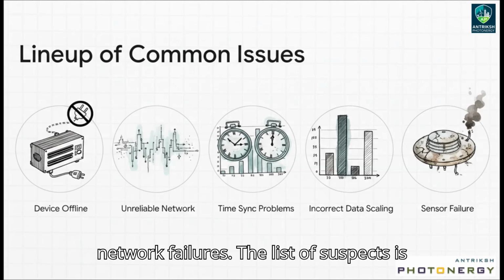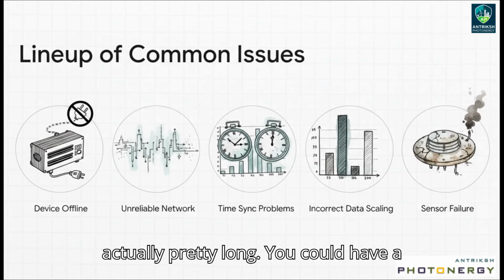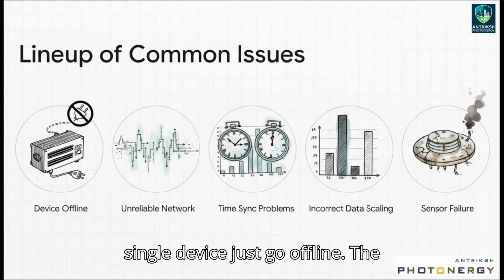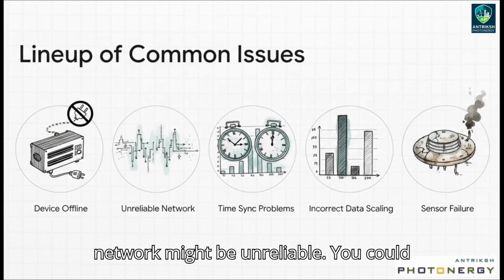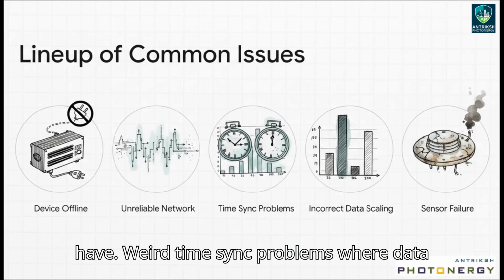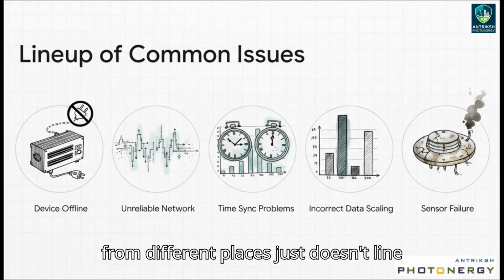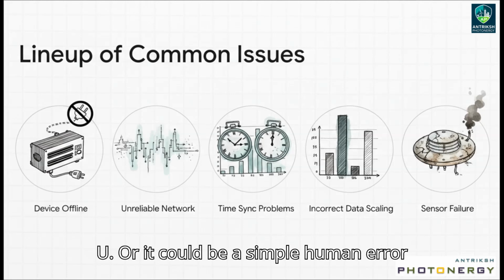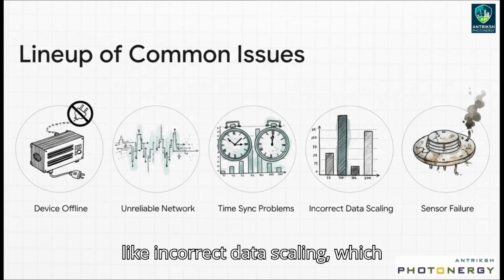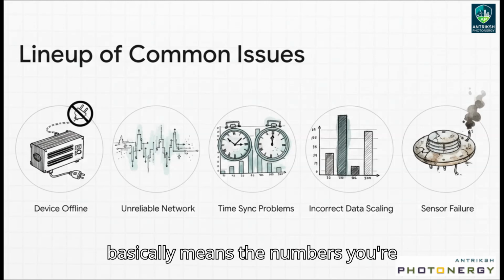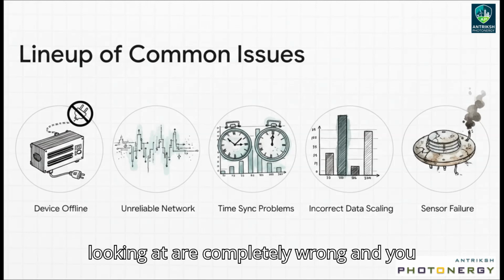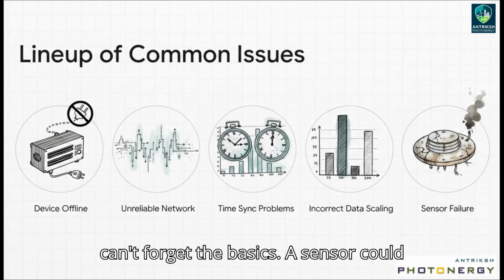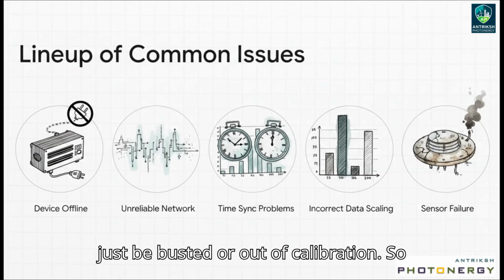And of course it doesn't just stop at total network failures. The list of suspects is actually pretty long. You could have a single device just go offline. The network might be unreliable. You could have weird time sync problems where data from different places just doesn't line up. Or it could be simple human error, like incorrect data scaling, which means the numbers you're looking at are completely wrong. And you can't forget the basics: a sensor could just be busted or out of calibration.